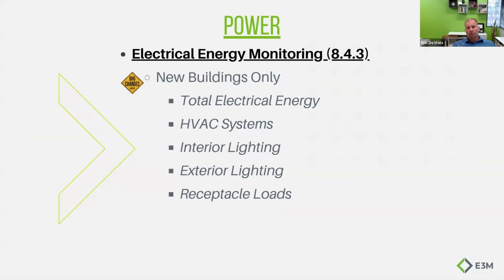Another big change, and I want to clarify this one: new buildings only, not an addition, not an alteration, a brand new ground-up building only. It now requires whole building electrical energy monitoring. You have to have power meters, either in your panel or secondarily added, to monitor your total energy use, your HVAC load, your interior lighting load, your exterior lighting load, and your receptacle load, and if it's a process building, your process load as well.